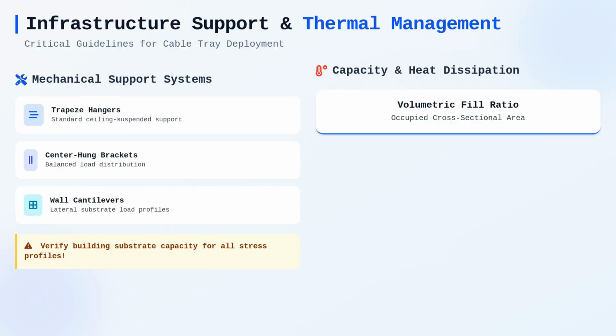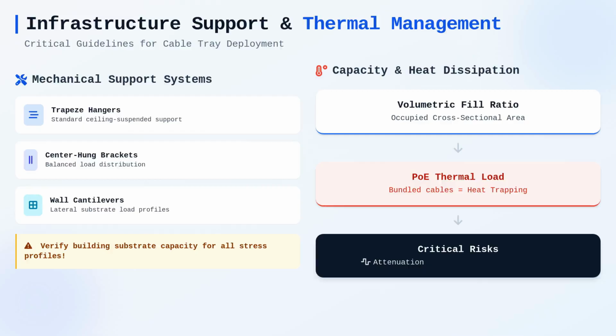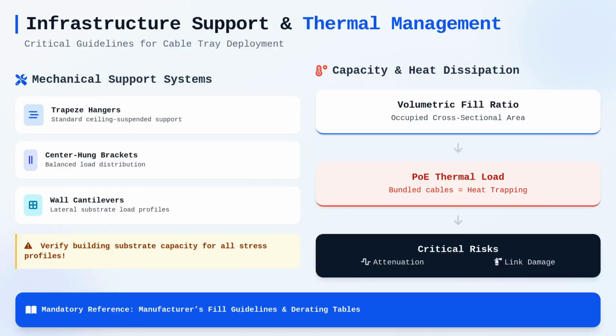When calculating the capacity of a tray, we look at the volumetric fill ratio, which dictates how much of the cross-sectional area is occupied by cables. For data centers and equipment rooms, this is not just about fitting as many cables as possible into a space. It is about maintaining the thermal dissipation characteristics. Power over Ethernet, or PoE, introduces significant heat during operation, and if cables are bundled too tightly, the heat cannot escape effectively, leading to unwanted attenuation or even long-term damage to the link. You should always reference the manufacturer's fill guidelines and derating tables to ensure that your design remains within acceptable thermal thresholds.